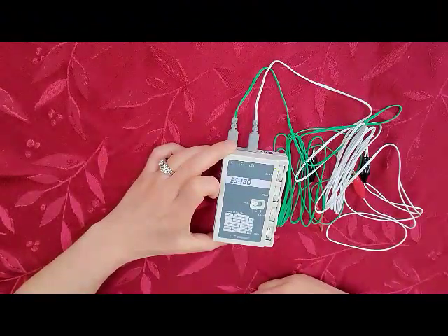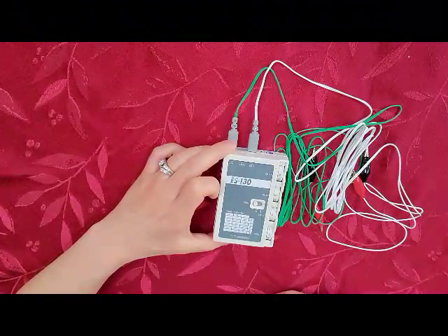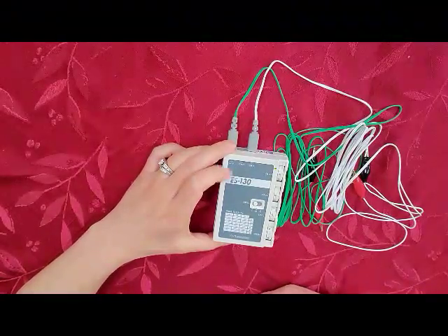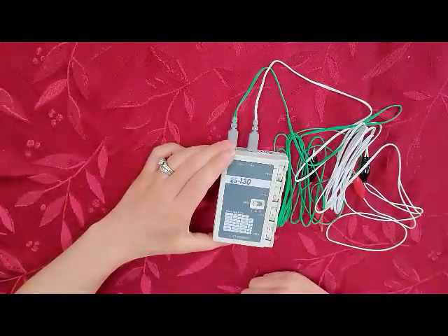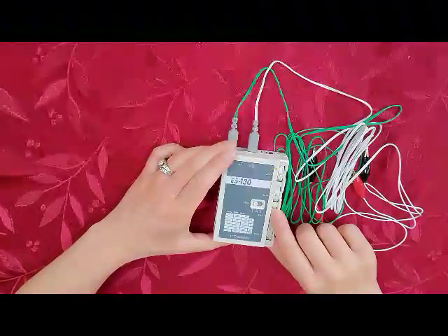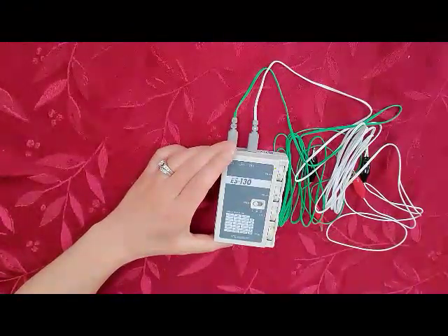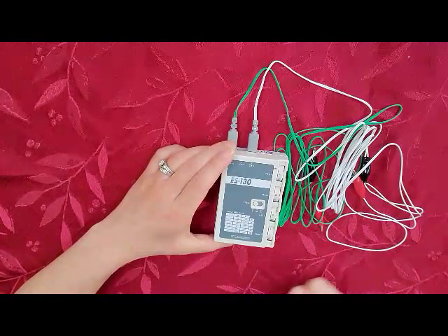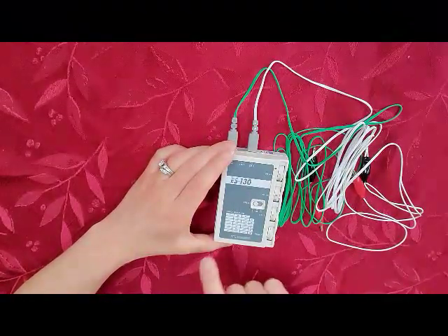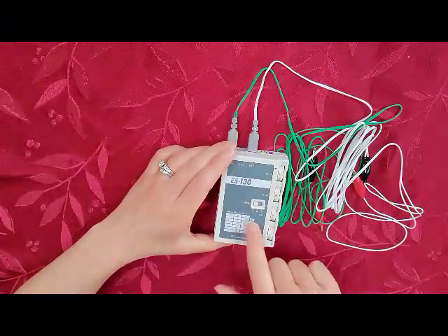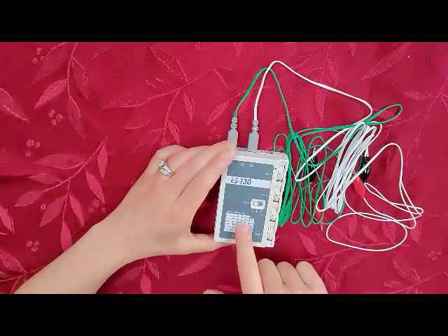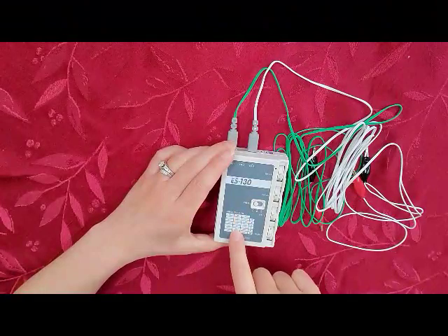Now, suppose we've completed this treatment and we wanted to move to a setting of 100 Hz. The very first thing we need to be sure to do is turn our channels off again. So now that the unit is off, we can adjust our frequencies. If we wanted to change our setting to 100 Hz, we go back to this table and find that 100 Hz is in the M column.